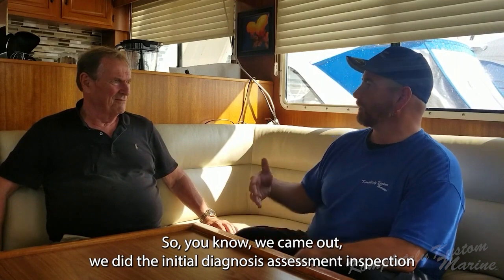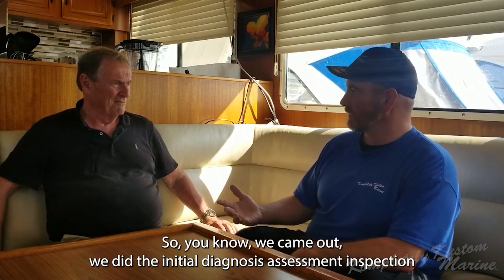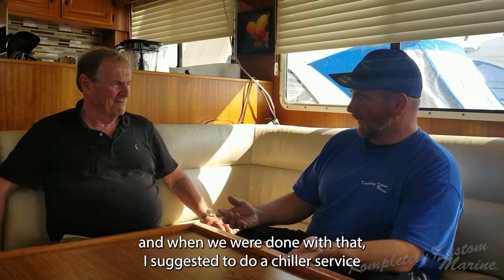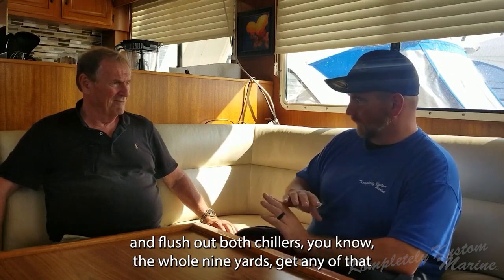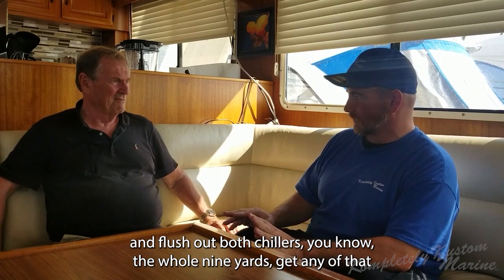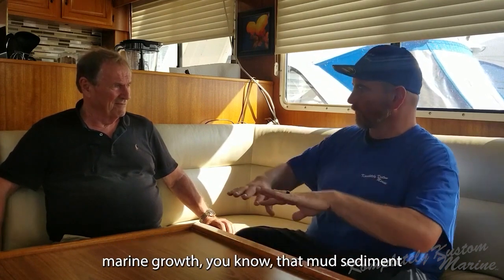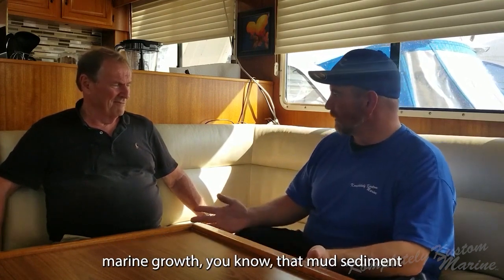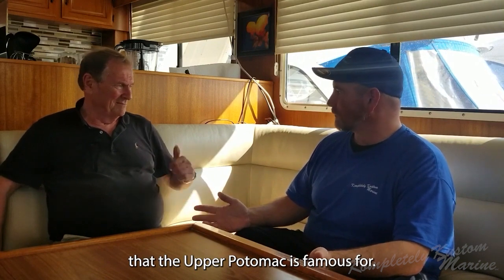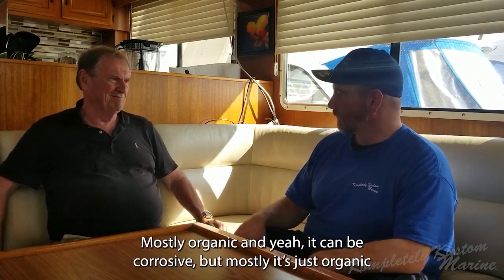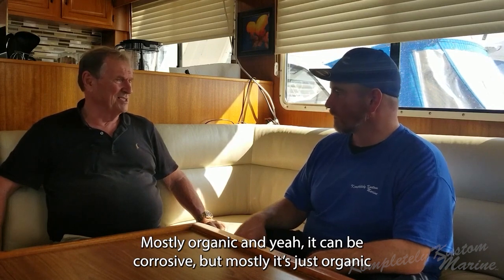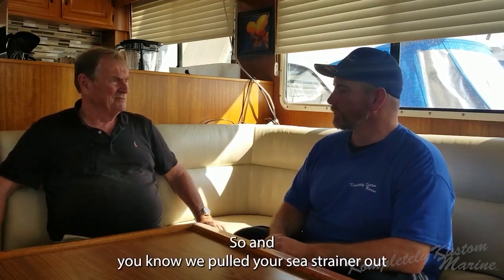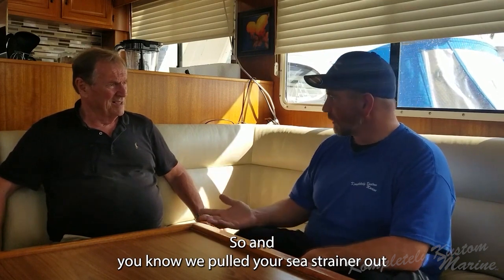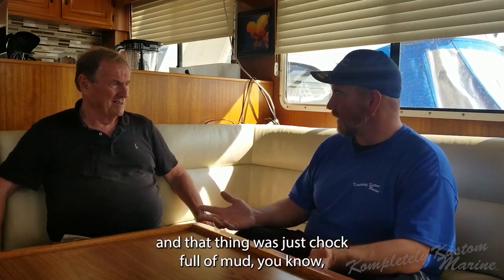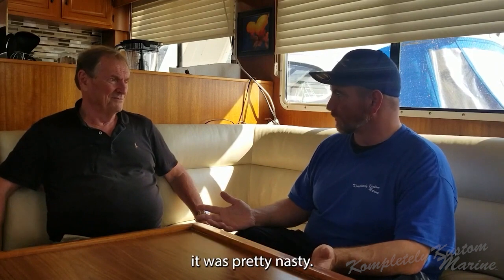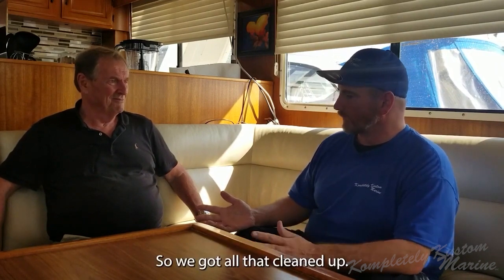We came out, did the initial diagnosis, assessment, and inspection, and when we were done, I suggested doing a chiller service and flushing out both chillers, the whole 9 yards, to get out any marine growth and that mud sediment the Upper Potomac is famous for. It's mostly organic, and it can be corrosive, but mostly it's just organic and forms a sludge. We pulled your sea strainer out, and it was chock full of mud, pretty nasty. We got all that cleaned up.